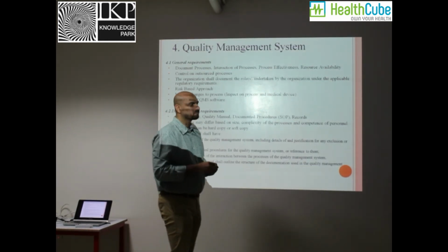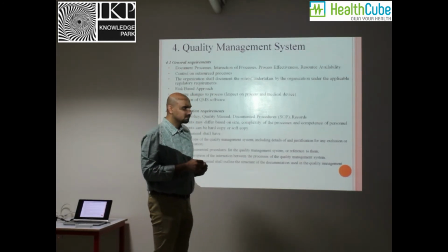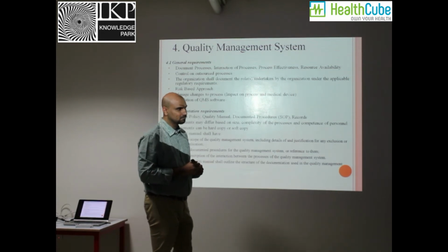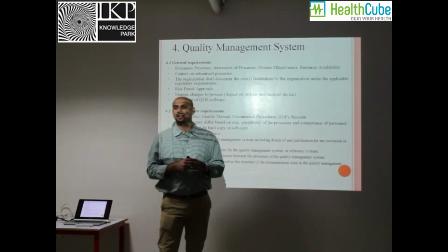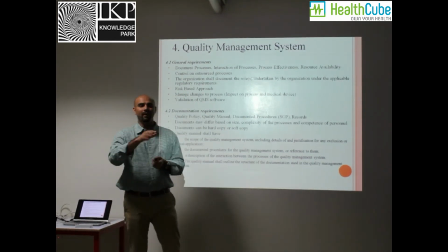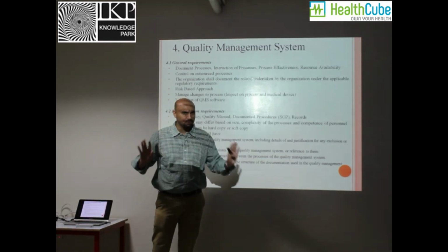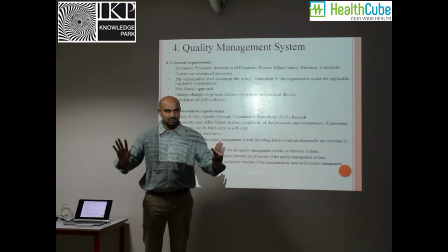So let's say the company which manufactured electrodes followed this process, got the ISO 13485 certification, and now next month decided to make implantable devices. What do they do now? Thank you so much for asking that question. You can always add your scope, you can always change your scope. There is a process associated with that. It's not going to happen one fine day just like that. So there is a process defined.